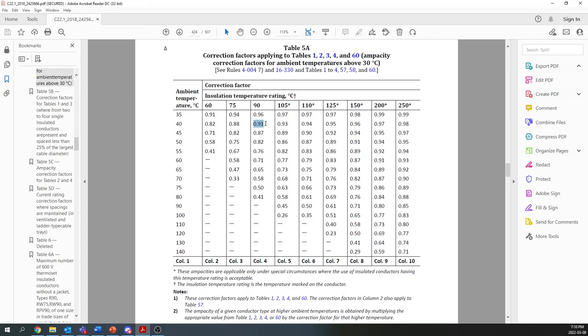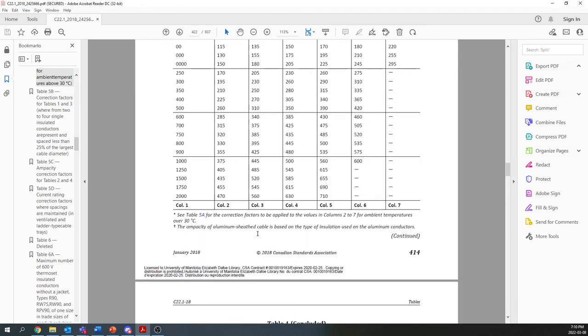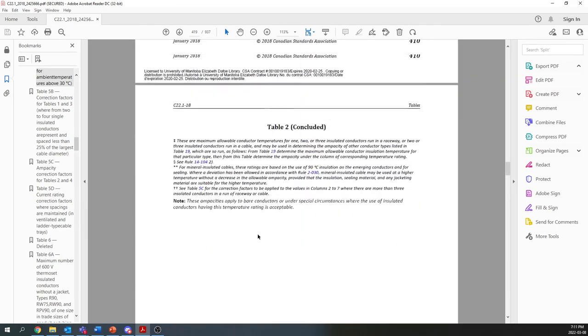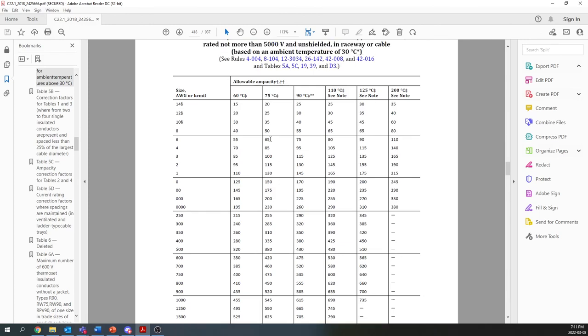So taking that into account and going back to table number 2, I'll do the calculation here: 0.91 times 85 is 77.35. So we're fine there. We can still use the number 4 for our 75 amp load. But for the 8 gauge, 50 amps, we're right on the cusp. Right on the cusp. Obviously 50 times 0.91 is going to be less than 50, 45 and a half.